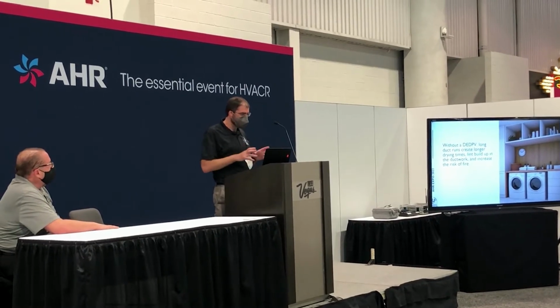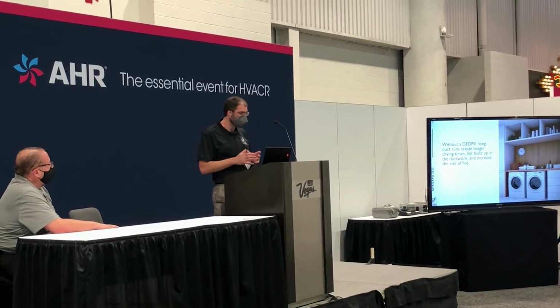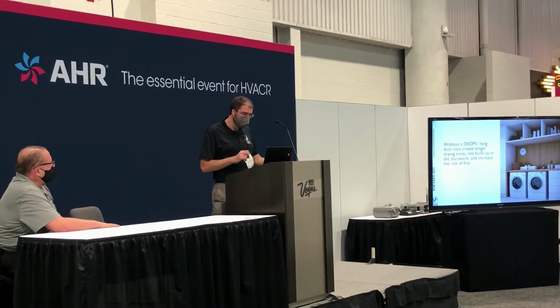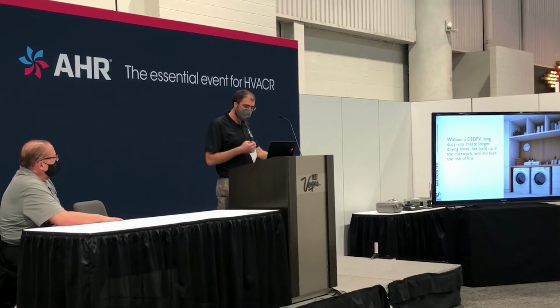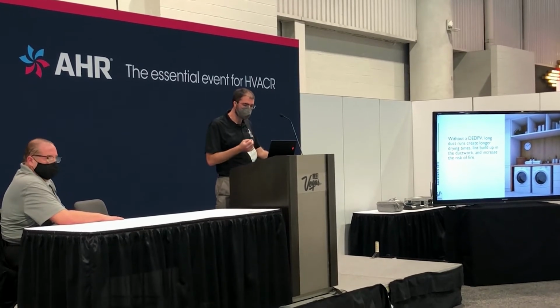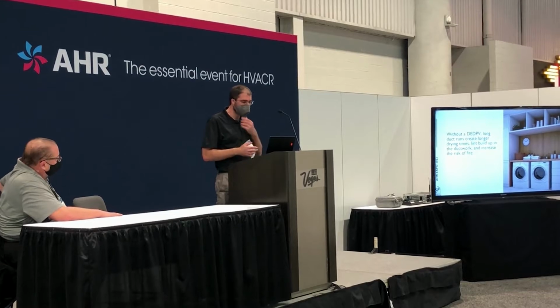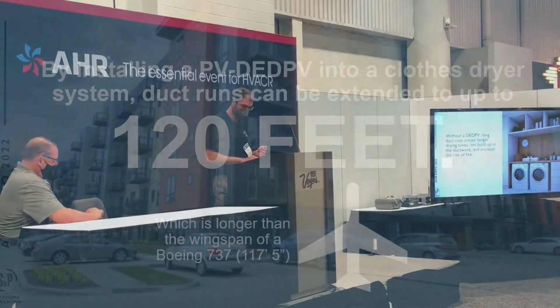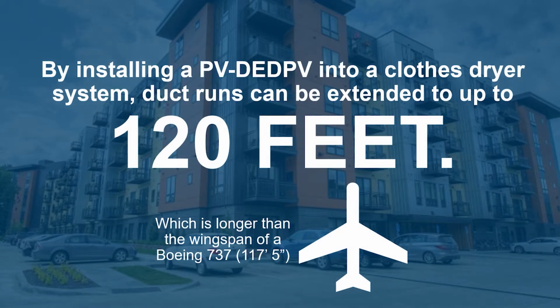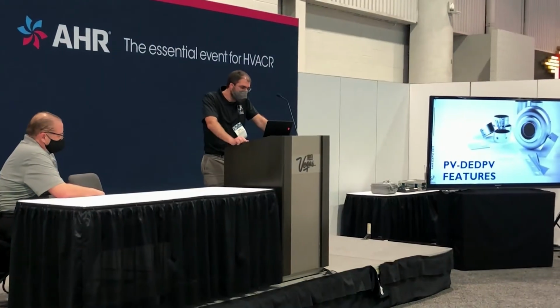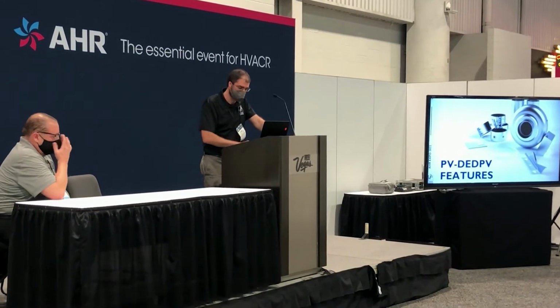And just to put a statistic to this, in 2010 through 2014, there were 15,970 home fires that involved clothes dryers or washing machines. And out of those, 92% of them originated from the dryer. By contrast, using a DEDPV in a closed dryer system, duct runs can be extended up to 120 feet, which is cool, that's longer than the wingspan of the Boeing 737 that I rode to come here to the convention. So now we're going to go over the features of our PV-DEDPV product.